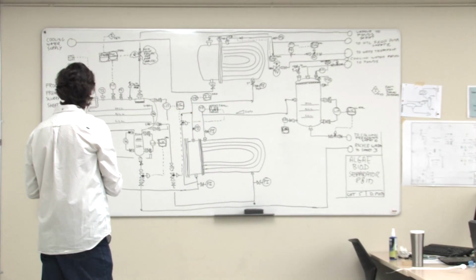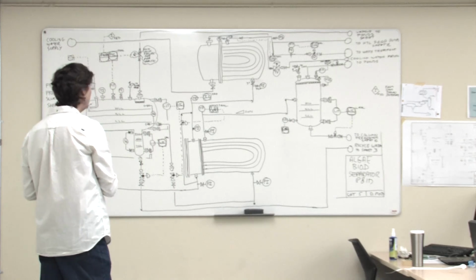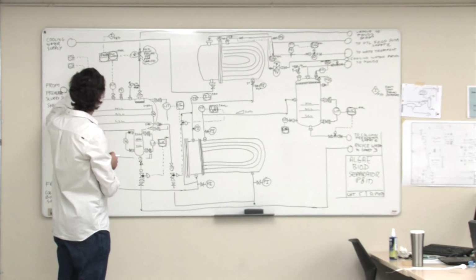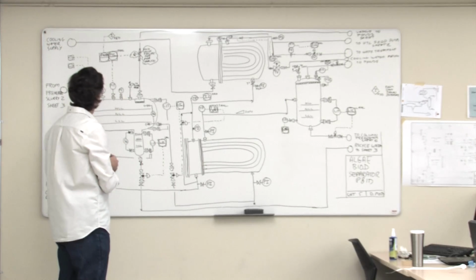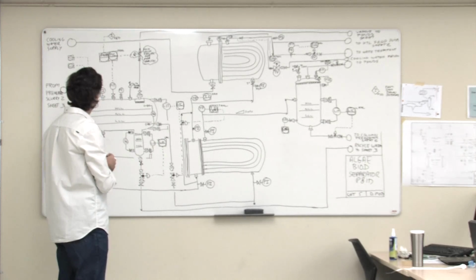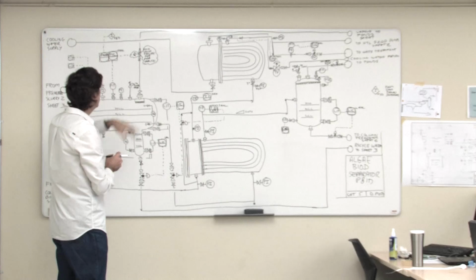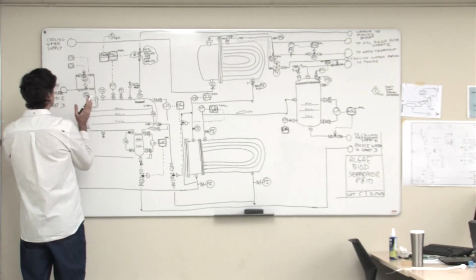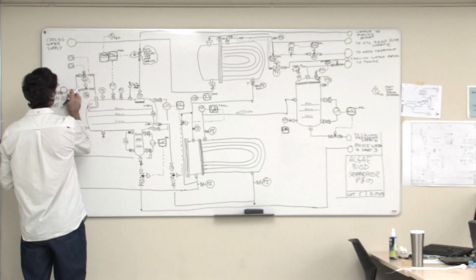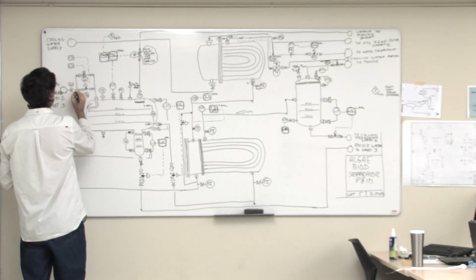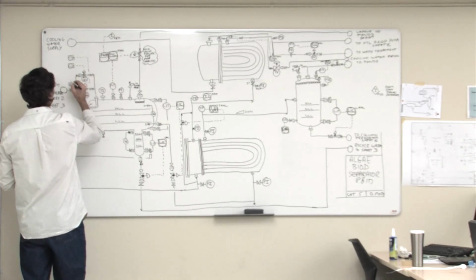Can I see any other real issues around interlocks? I think the biggest problem I would see here is a problem with those valves failing or sticking open and us overpressuring this vessel. We've got the relief valve ultimately to protect us. So if I'm really worried about that, then about all I can really do is put another block valve in here. So this would be basically an emergency valve, and we're going to tie it in maybe to that interlock. So what I'm going to do is show that interlock FSD sending a signal into this valve.